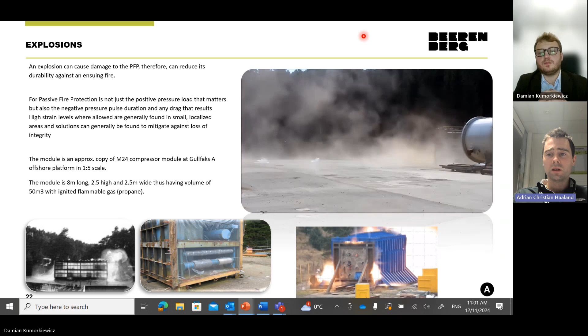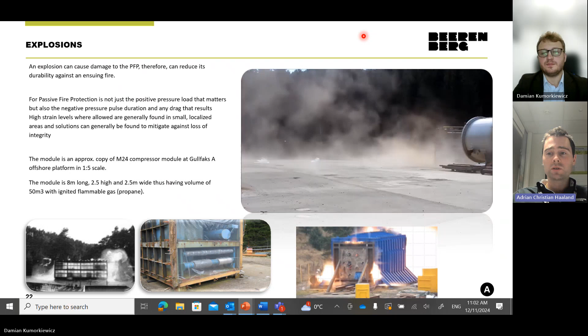And although you might think that 1 bar is not so much, I have 5 bar in my car tire or something, but on a 1 square meter area, 1 bar explosion pressure is equal to 10 tons of impact load. So you can imagine having 10 elephants on top of a square meter of your system. It's quite a harsh impact, and we have tested products previously which have not been up to the spec, and if your products first start to fail, you won't even find the debris. They will be out in the forest several hundred meters away due to the extreme pressures. These are forces that can bend solid steel beams. It's not to be underestimated.